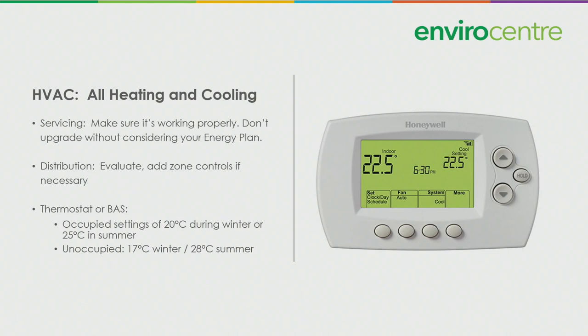With your thermostat or your building automation system, you should set occupied settings of about 20 degrees during winter or 25 in the summer for good energy efficiency. When it's unoccupied, set them back. On the weekends, you can set them back to 17°C in the winter or 20, or you set them forward to 28°C in the summer. More energy savings.